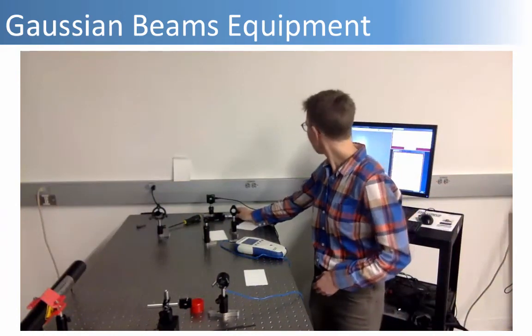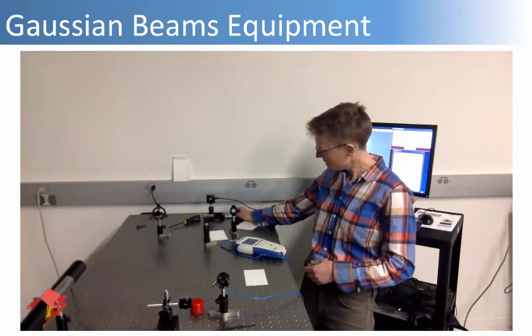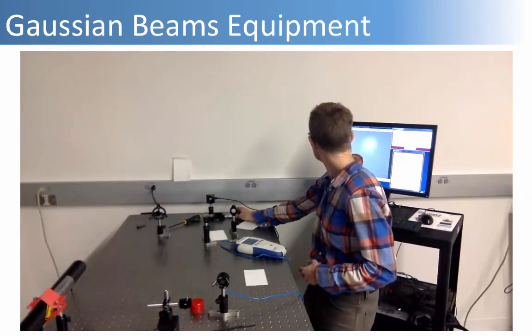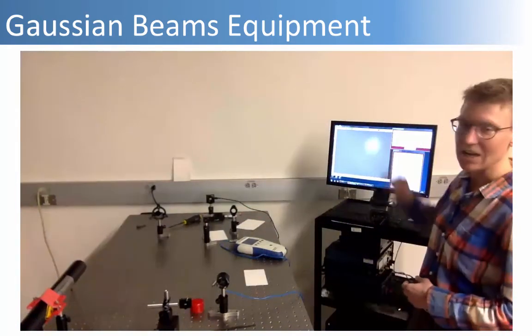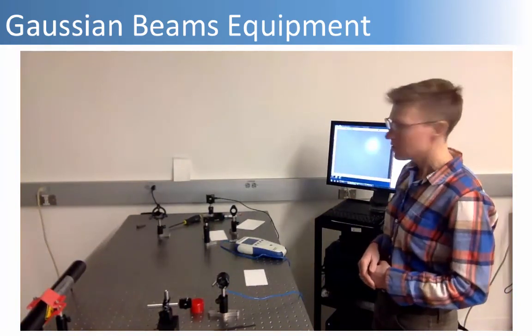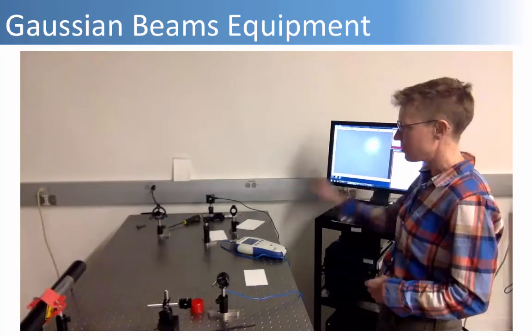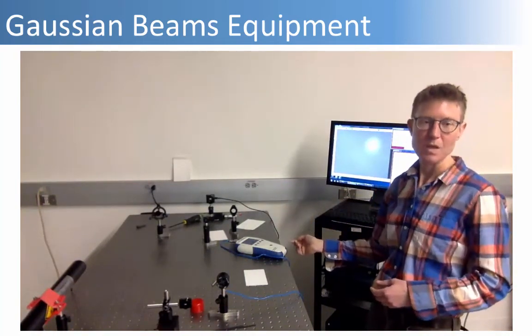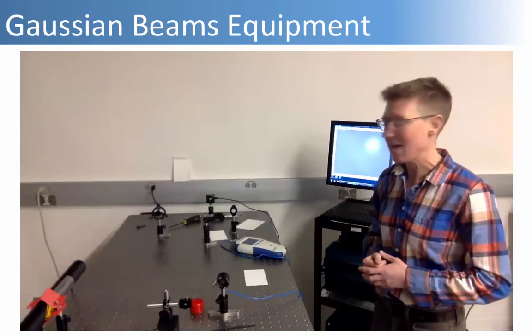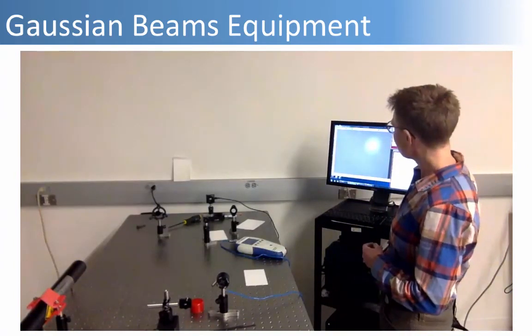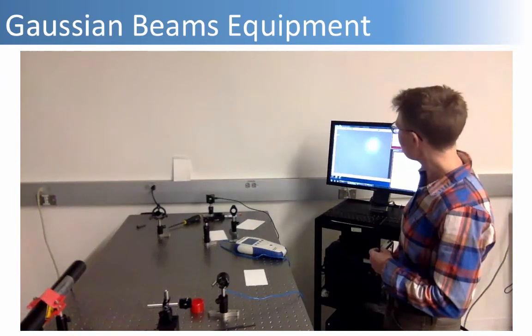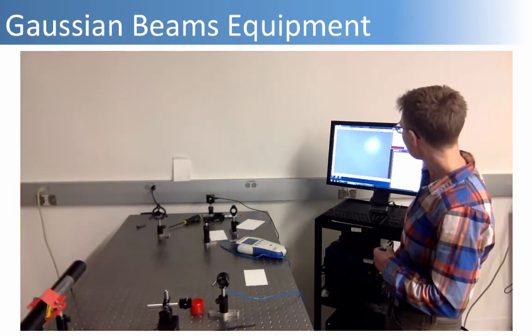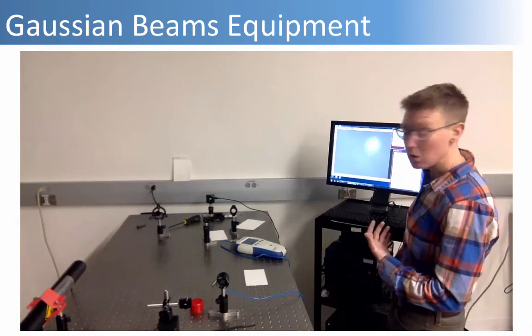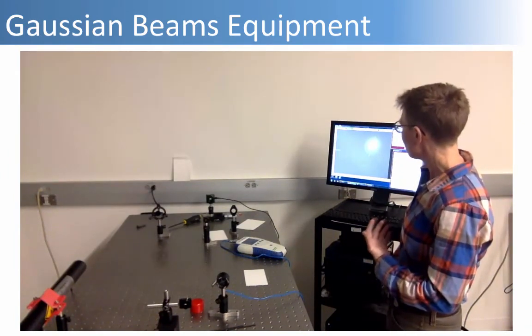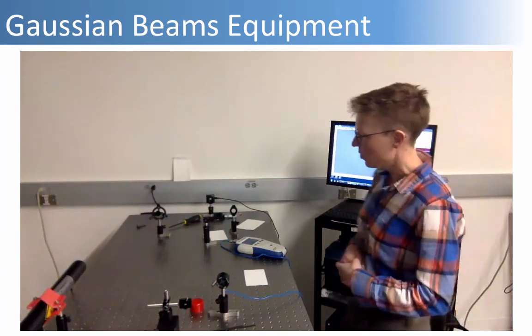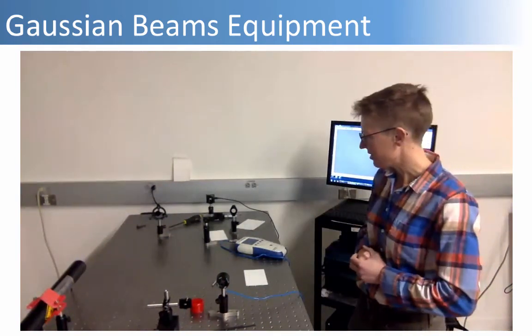We have the cameras on a translation stage, and as you turn the knob, you'll see that the position of the beam changes. So what I want you to do is to mark the starting position and ending position for a particular translation and calculate the pixel size based on that. You can use other tools like drawing tools. There's a line drawing tool here where you could, for example, draw a line right through your mode or multiple lines. You can erase your lines.